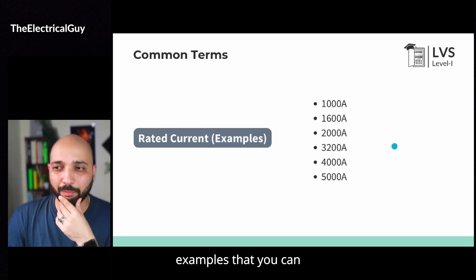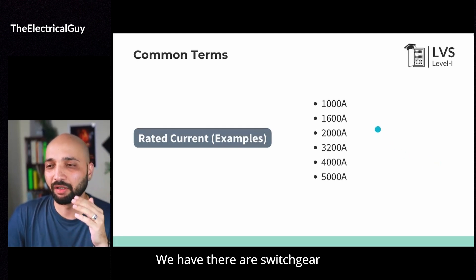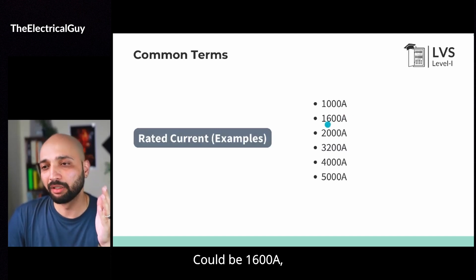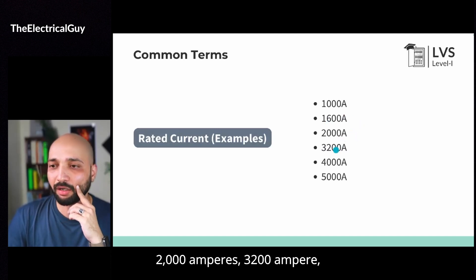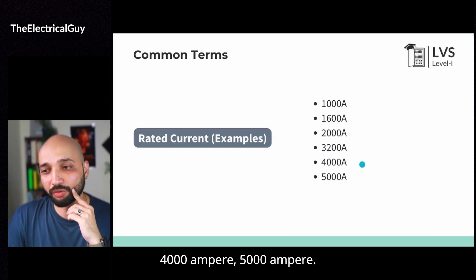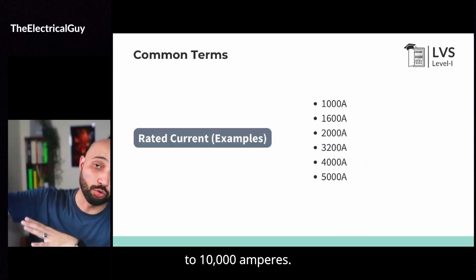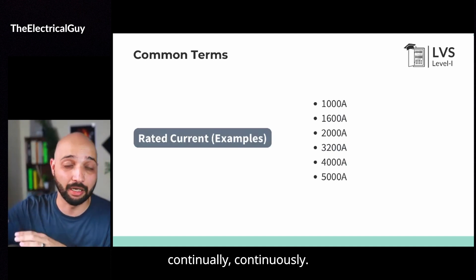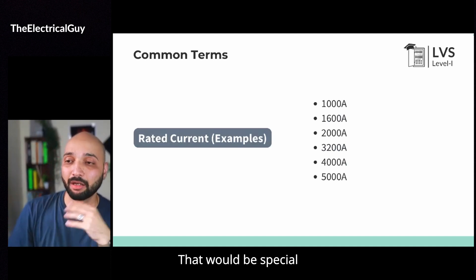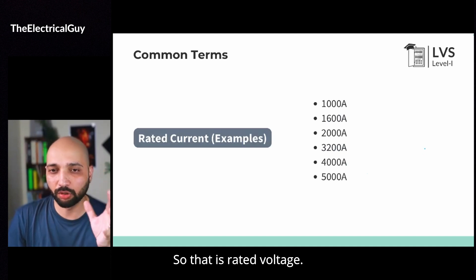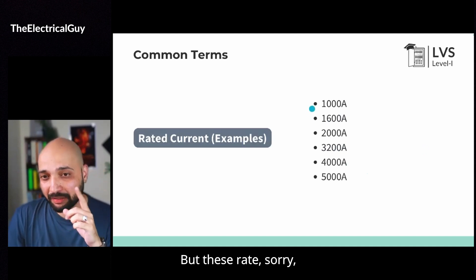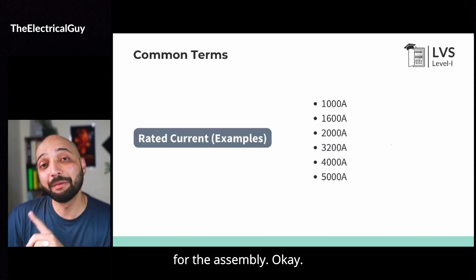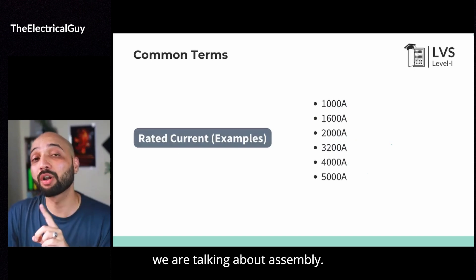So it's very important that you select this based on what the system current is. There are some different examples you can see on your screen. We have switchgear capable of carrying less than 1000 amperes, could be 1600, 2000 amperes, 3200 amperes, 4000 amperes, 5000 amperes, and it could go also to 10,000 amperes. There are switchgear available which can carry 10,000 amperes continuously — that would be for special applications. So that is rated current, but this rated current is for the assembly, not the circuit.